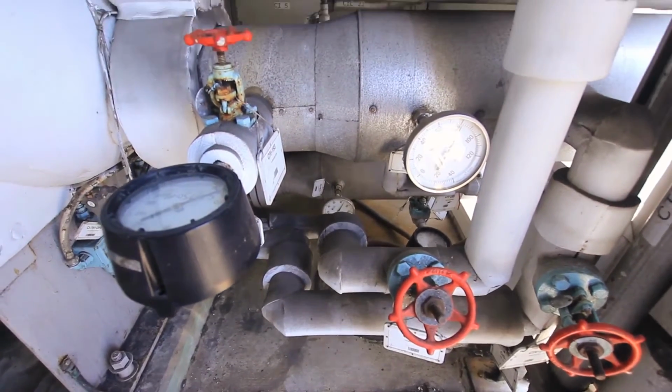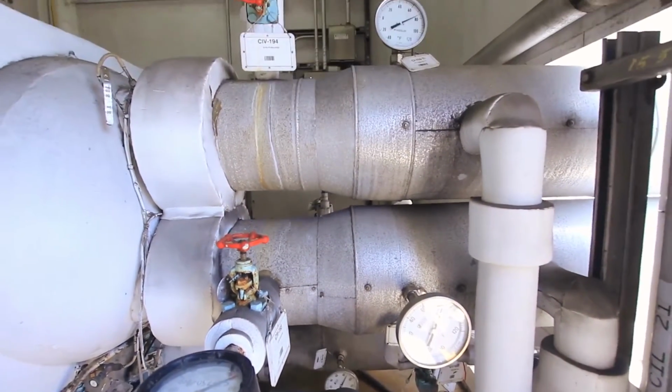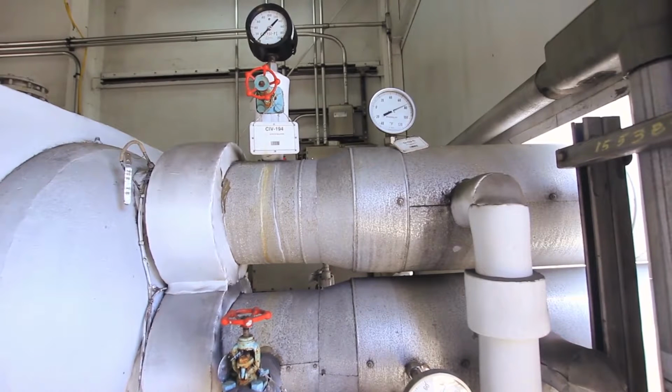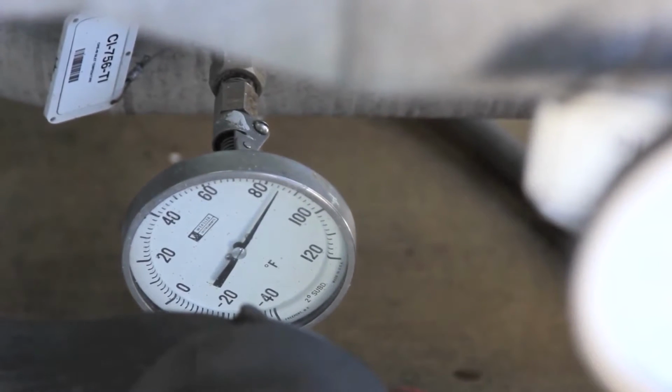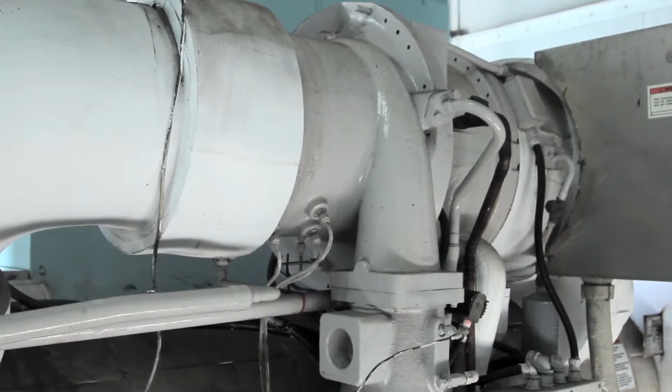It has a cylinder which controls the outflow off of the impeller. It still has the pre-rotation vanes controlling the gas flow to the inlet. They both operate off one mechanism inside, which is driven by the oil pressure from the machine.